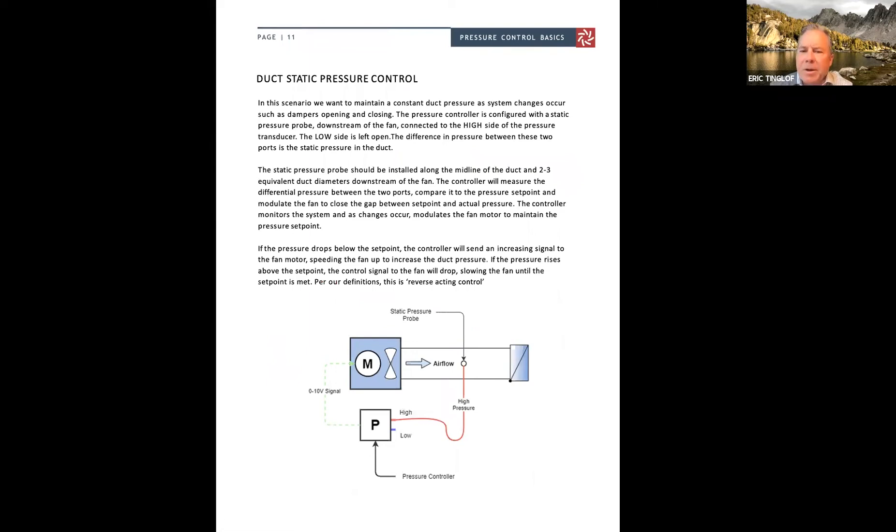So let's talk about a couple different scenarios here. If we're just trying to measure duct static pressure control, you'd have a static pressure probe mounted in the ductwork, and then you would connect that static pressure probe on the high side of the pressure control. The low side is left open to the atmosphere. And then as the pressure rises above our preset set point, the control signal to the fan drops. So that's what's called reverse acting control. The difference in the pressure is the error. We're trying to minimize or remove that error to get us back to set point.